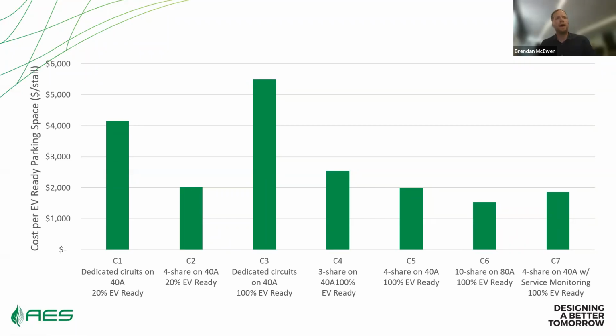It's worth noting that right now there are relatively few EV charging service providers that can serve this type of building, although they're definitely out there. What's required under current building code rules, if you're going to do this, is either 80 amp chargers, which would be relatively more expensive, or an integral circuit breaker in the chargers, which most don't currently have, and products would need to be reapproved, which is why manufacturers haven't done that. That would be a fairly low cost addition, but it's the challenge of getting reapprovals for products.